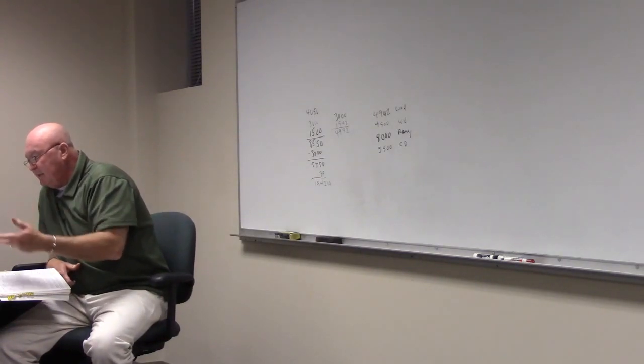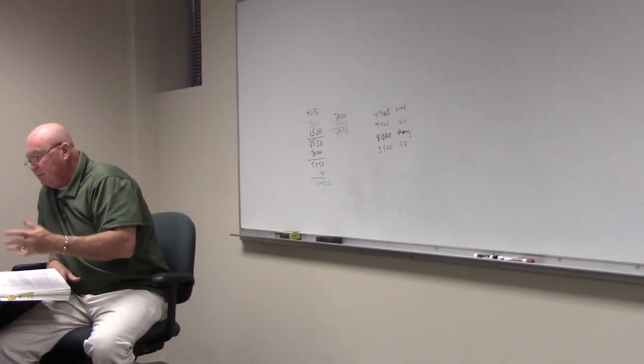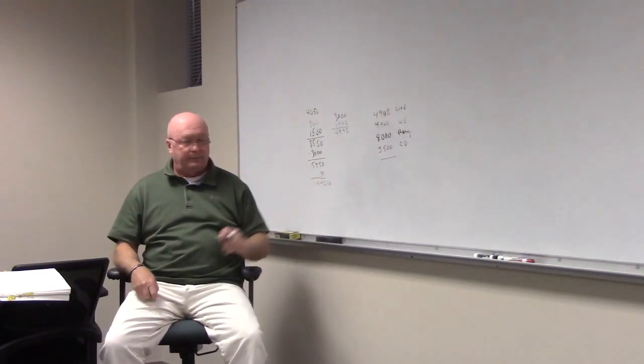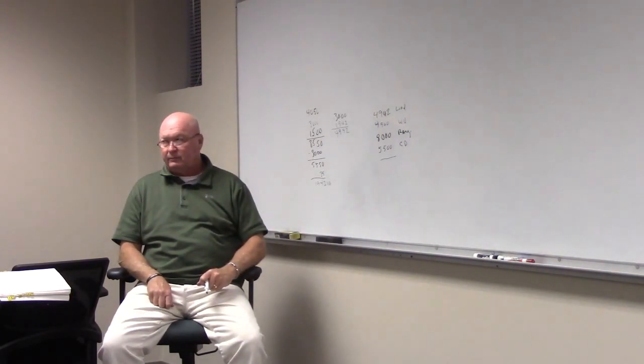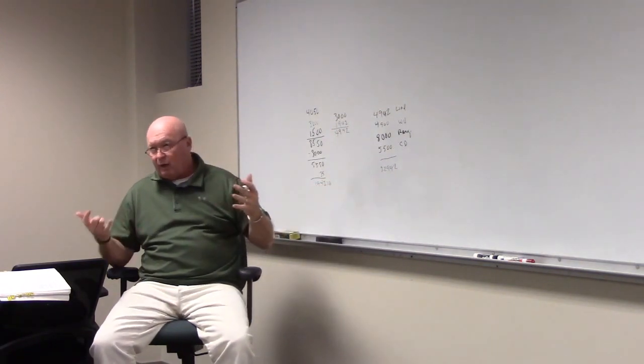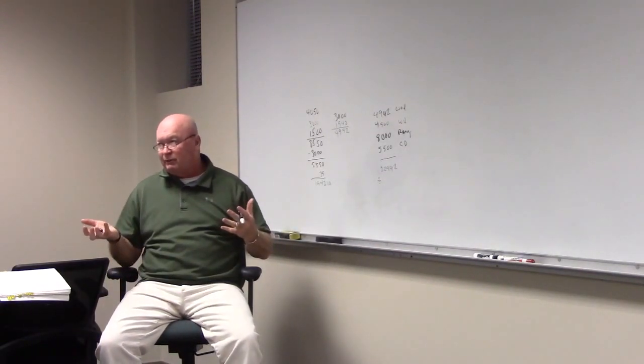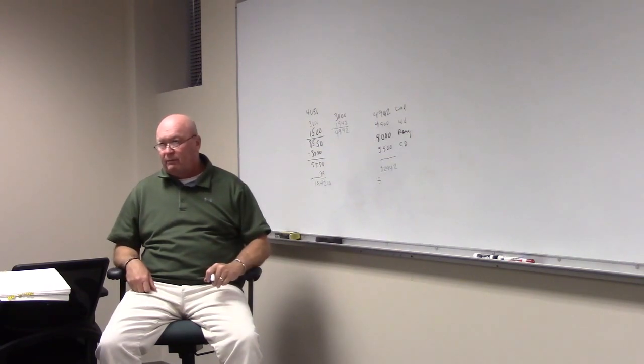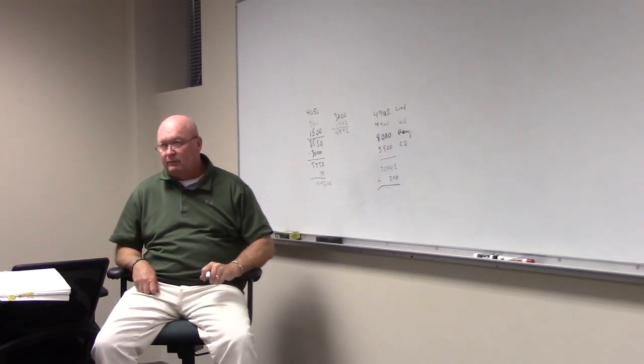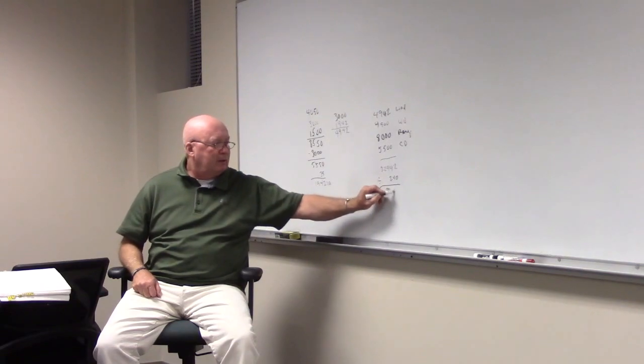So now we're just going to total the loads. 4,942, 8,000, 5,500, 4,500. And how much are we going to get? Should be 22,942.5. Yeah. That's watts, right? Now what do we need to do with that watts to get amps? Because to figure our wire size, we got to get the amps, don't we? Divide by 240. And that equals what? 96 amps, roughly. I agree with you.